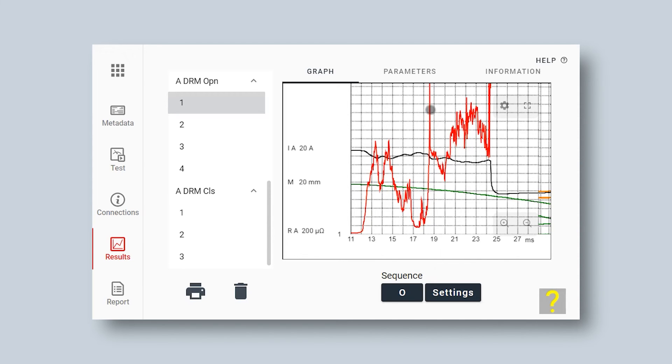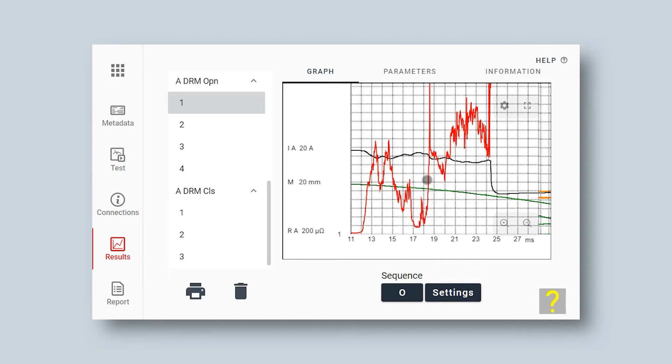Second point. I can see my main contact release, the red graph, where the resistance makes a big step to a higher resistance level. A step from closed circuit breaker at micro-ohm level up to milli-ohm level at about 18 milliseconds.